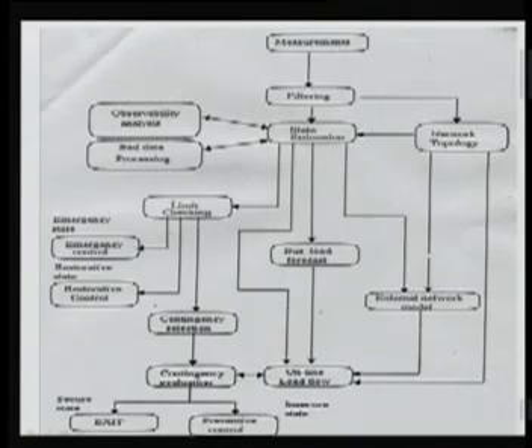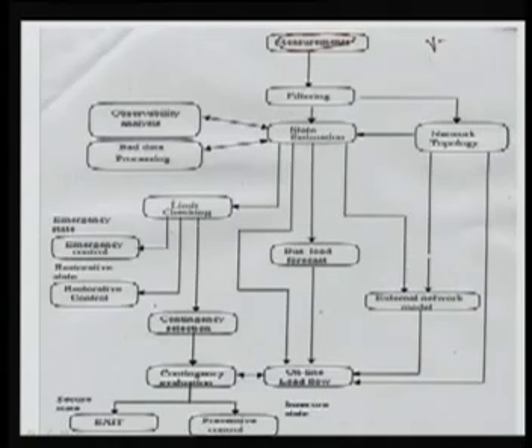Here again, the data are measured from the RTUs. We are getting the measured data. These measured data normally will have bad data. Bad data may be of two types. For some data, by looking at the information you can directly say that it is wrong. For example, suppose you are measuring a bus voltage at some point and it is 2 per unit. This shows that, in a running power system, it is not possible that the voltage magnitude is 2 per unit.